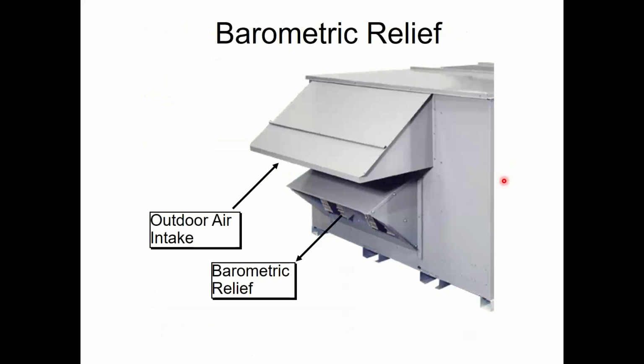If I'm going to suck extra outside air into the building, I need to have a pathway to get extra air out of the building, right? I can't just suck air in and then the building blows up like a balloon and explodes. That doesn't make sense. So if I don't give it a good pathway out, it'll find its own pathway, and frequently that means the front doors. The front doors will have trouble shutting. When you're on an economizer day, you suck a boatload of outside air in, and then your front door won't shut, and you literally have to pull it with your hands. It's ridiculous. So instead of doing that, I need to find a pathway to get it out.